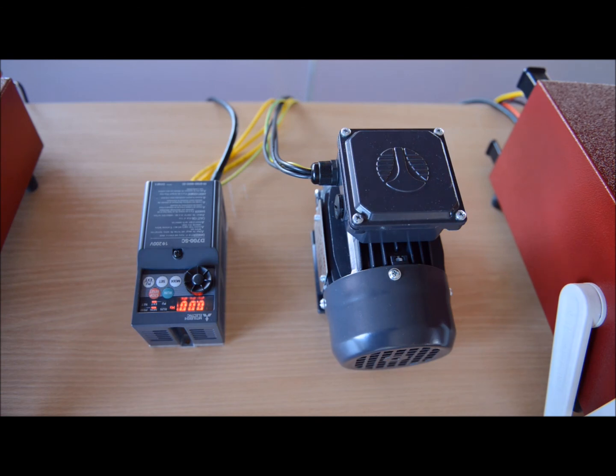Okay, so what we've got here is a Mitsubishi Electric AC input, AC output, single phase in to 3-phase out PWM motor drive inverter. So it's a frequency converter, and that's going to be driving a 3-phase motor at the output. So we are, just a quick reminder, going to be measuring the AC input and the AC output, and comparing those powers and looking at the electrical efficiency of this device, including losses in the rectifier, across the DC bus, filtering, and at the PWM inverter output.